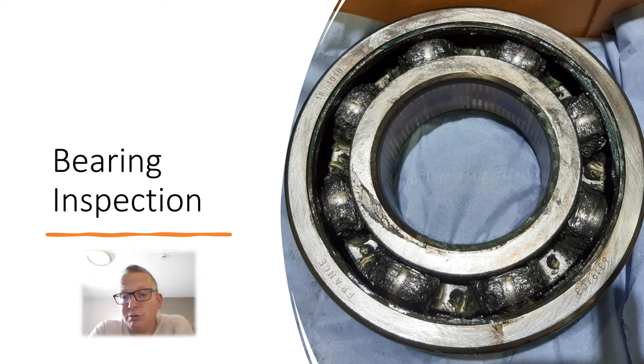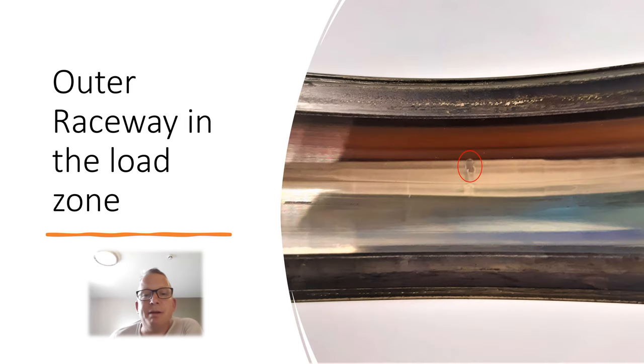So they took it out because it's super critical and they don't want any risk of failure. That's the bearing and when we split the bearing here, so this is the lower half of the bearing. You can see how it gets wider there. So this is actually in the load zone in the bearing.